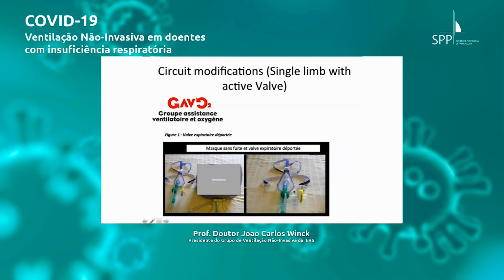So in this situation, you have a disposable non-vented mask. You have the blue elbow, then the circuit, and the ventilator, and a yellow bacteriological filter coming out of the ventilator. Then you have the active valve here, and some diversion, which is the expiratory valve, and you have the filter. So would you agree that this is a possibility to avoid the risk of dispersion of particles coming from the patient?